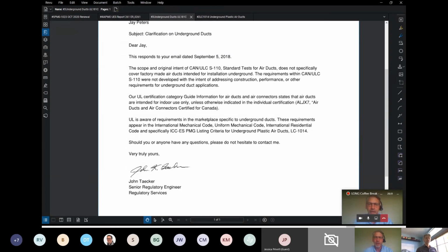Another manufacturer of underground duct systems, generically known as FRP, fiberglass reinforced plastic, unlike Blue Duct, can also be applied inside the building envelope or in occupied space. Because of that, they have to meet UL 181. So for any of you who've worked with that product, you'll see they meet that requirement. Understandably, an engineer may then assume they need UL 181 for underground ductwork too, when in fact you don't need it. So that's potentially the origin of the confusion in the marketplace.